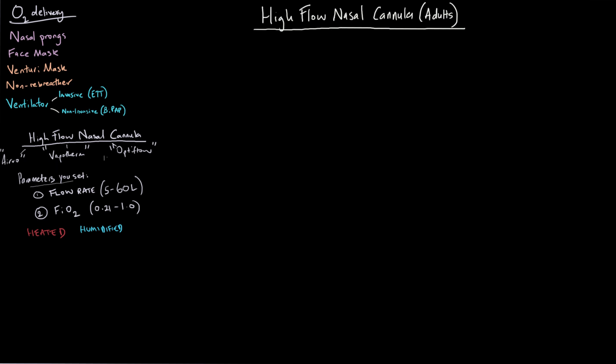High flow nasal cannulas are different in that flow and FiO2 aren't as closely connected as with nasal prongs or regular face masks. On a high flow nasal cannula device, you independently set a flow rate and an FiO2. These devices typically deliver between 5 and 60 liters per minute, and a blender system allows you to deliver, for example, 40 liters per minute at 21% FiO2, or 10 liters per minute at 100% — you choose both independently.